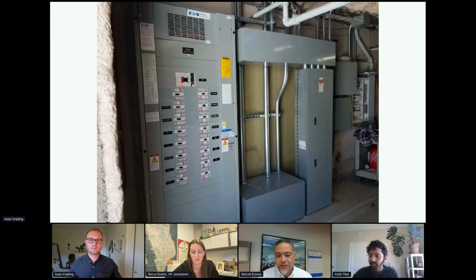We opted to replace the entire gear because it was old equipment. There were no longer parts available for this, and in the past we already had issues with poor connections or faulty boxes throughout all the years. It was there during the original construction. The one thing you don't want to find out later on in this project is that you burn out a brand new piece of equipment, so we definitely didn't want to do this. We also didn't want to have an additional shutdown of the building if we had to do an electrical project. So we decided to do everything all at the same time.